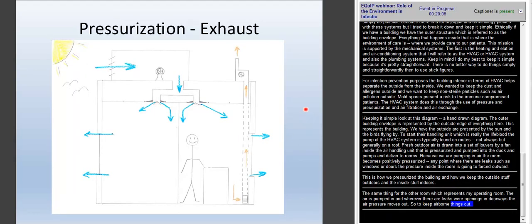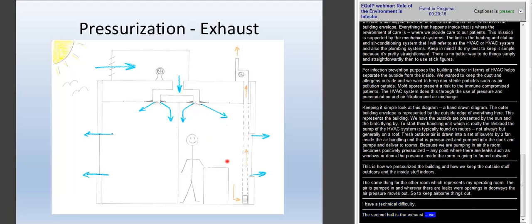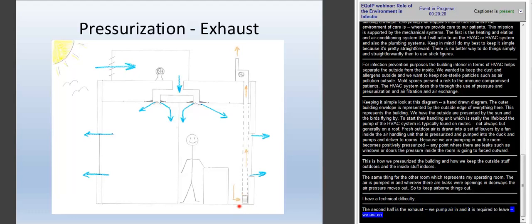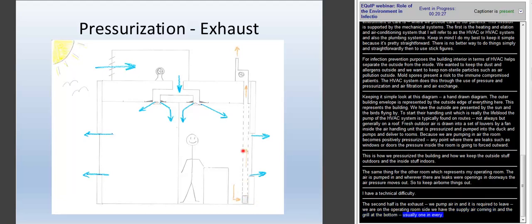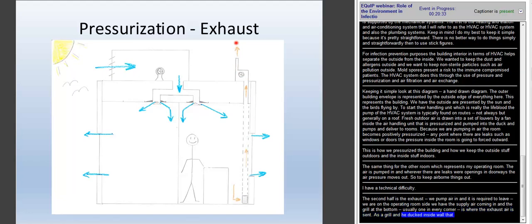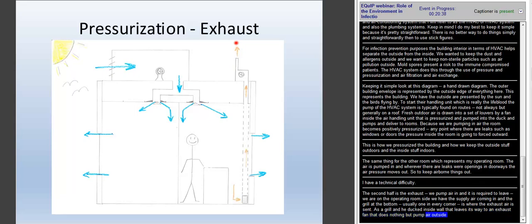Here we go. So the second half of this is the exhaust. We pump air in, air also is required to leave. If we stick on the operating room side, we have the supply air coming in, and that grill down at the bottom, there's usually one in every corner or every side of your operating room, is where the exhaust air is sent out. There's a grill, there's a duct inside the wall that leads up to an exhaust fan that does nothing but pump air outside the building and exhaust it straight out. That's typically what we'll see in an operating room, a designated exhaust.